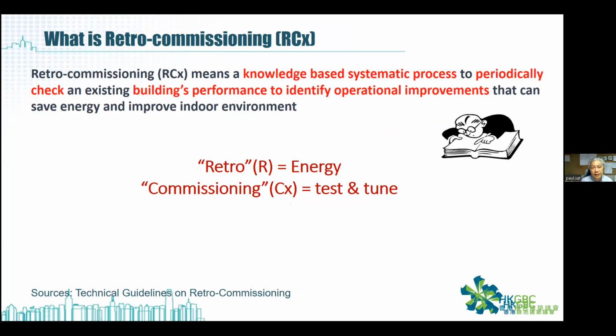Okay, so in here you can see that retro-commissioning is a knowledge-based systematic approach for Hong Kong in order to check the existing building performance, to identify some of the opportunities for improvement for energy savings and also improve the indoor environments. Retro-commissioning is composed of two parts. One is the retro, meaning energy, and the other is the commissioning, meaning testing and tuning. Retro-commissioning does not ask people to replace or renew something, but to do some commissioning, testing, tuning and modifications, something like that.